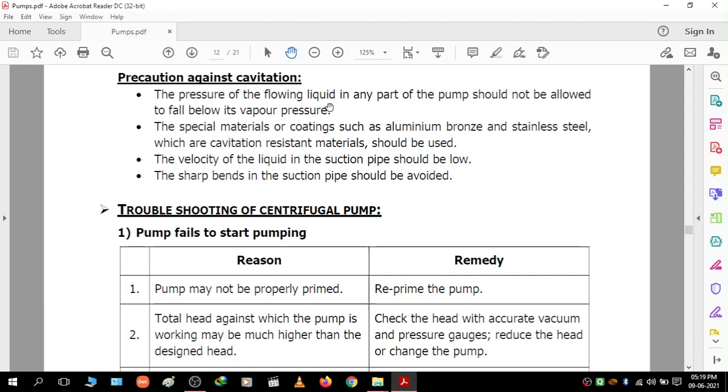Precautions against cavitation: The pressure of the flowing liquid in any part of the pump should not be allowed to fall below its vapor pressure. Special materials or coatings such as aluminum bronze and stainless steel which are cavitation-resistant materials should be used.